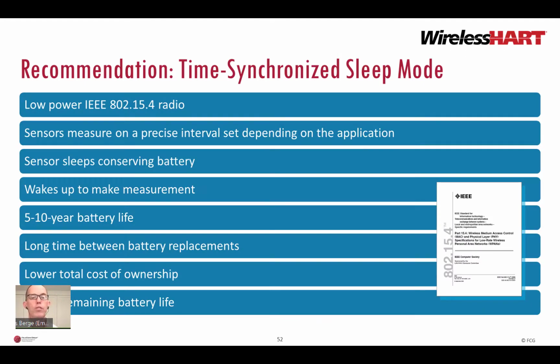WirelessHART solves this with time-synchronized publisher-subscriber, or pub-sub, communication. Every sensor has an internal clock and measures on a precise schedule or interval set depending on the application. For instance, a corrosion sensor may only need to measure and publish the data twice a day. A vibration sensor once an hour, a steam trap sensor once a minute, but a flow sensor once a second, or anywhere in between. The sensor is in fact sleeping most of the time, thus conserving battery.